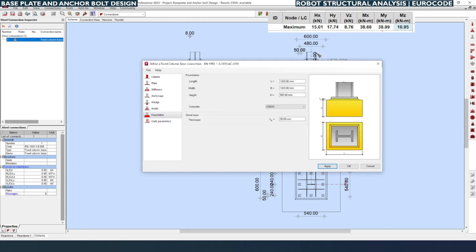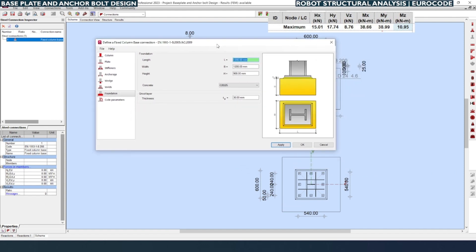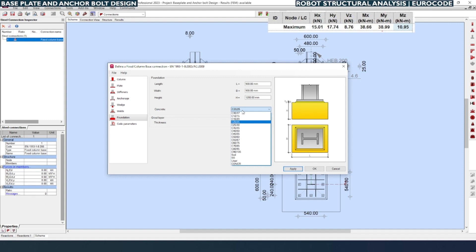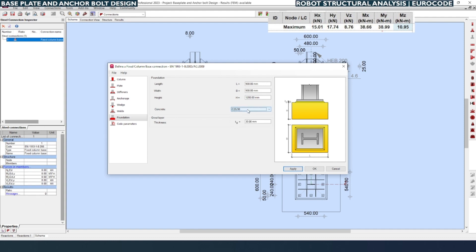Next, coming to the Foundation tab. The foundation size — since the base plate is 600 mm, we can assume the foundation (pedestal) as 900 mm. The foundation is essentially the pedestal or column which is going to hold the base plate. The height can be given as 1200 mm, which is more than the anchor bolt length. The anchor bolt penetrates into the concrete by 800 plus 100 = 900 mm, but we consider 1200 mm. The concrete grade is set here to help calculate the bonding stress of the anchor bolt with the concrete.